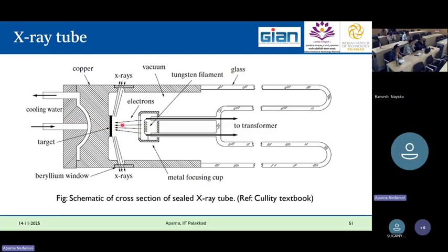There is a voltage difference between the anode, which is the target, and the cathode, which is the source of electrons. So the electrons are drawn towards the anode at a higher speed. If that voltage is not maintained, this speed is not maintained. Once they are drawn towards the target at higher speed, the electron with higher kinetic energy hits it, and the impact is so significant that on copper, if the target is copper, copper can have different electrons at different orbitals, right?